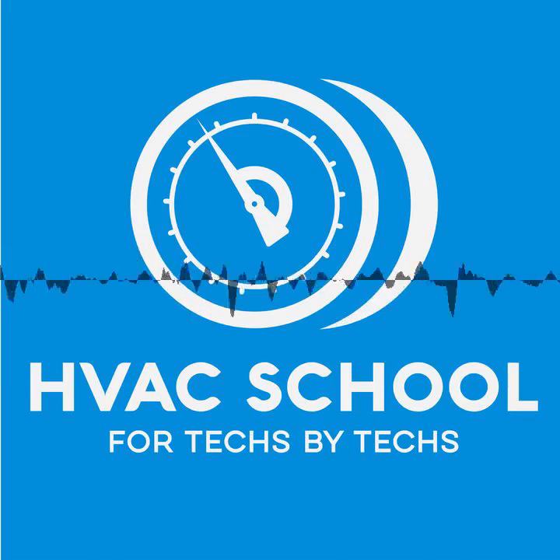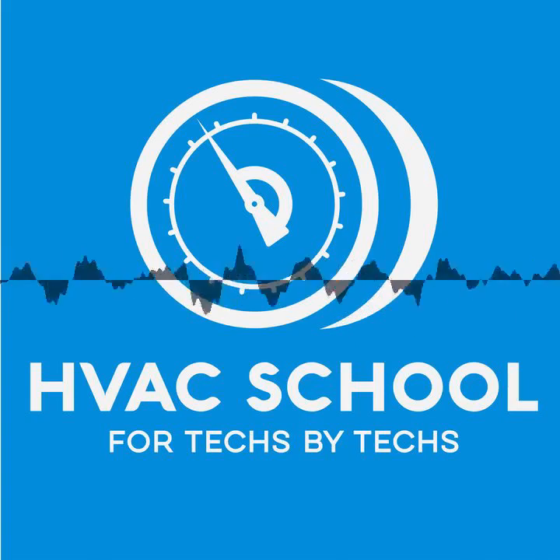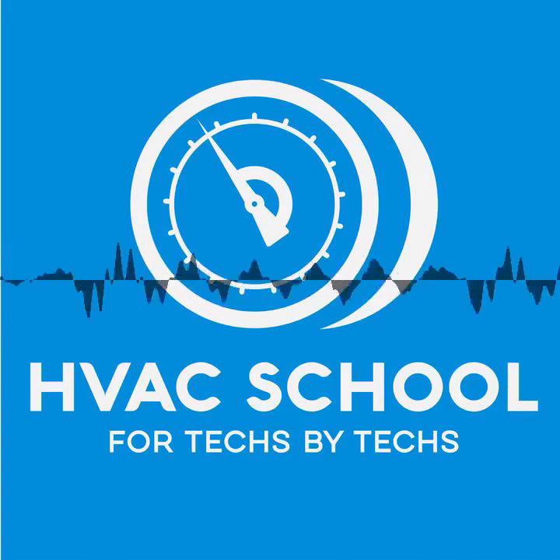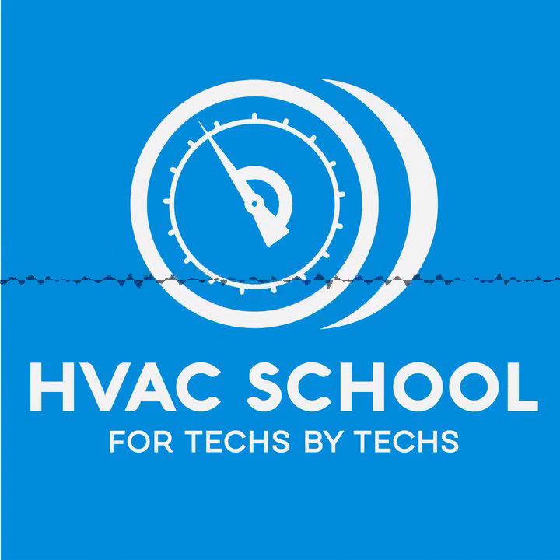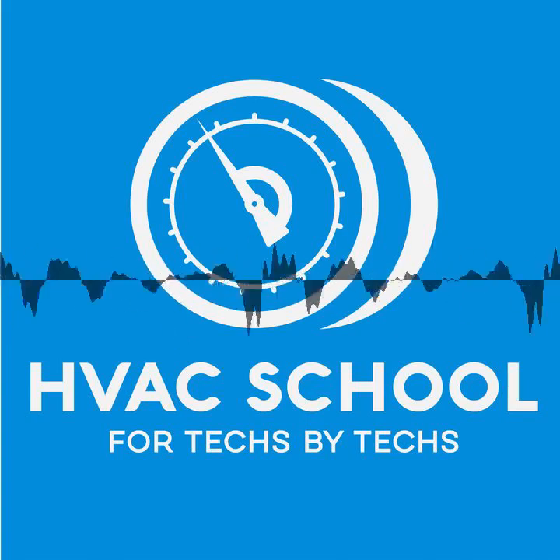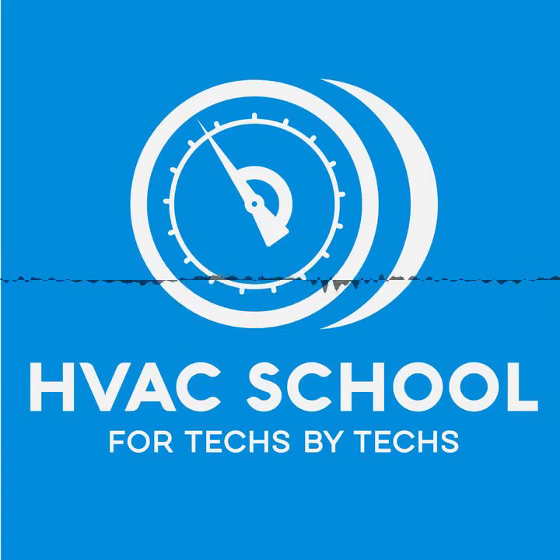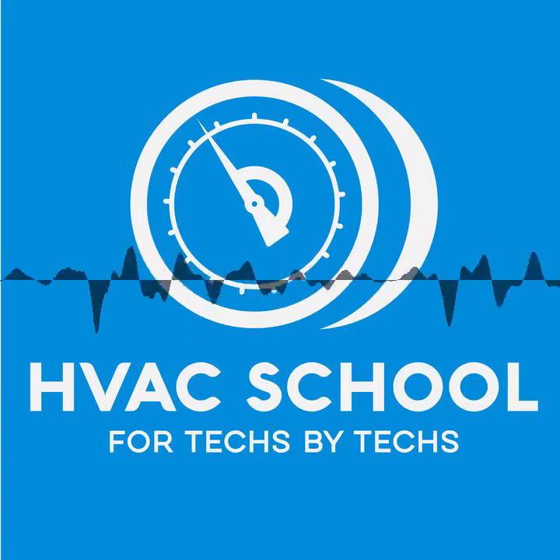Yeah. I think it has to do with energy saving and not getting liquid back, because these cap tube machines don't have receivers or accumulators. So I guess they're trying to assure that they don't get liquid coming back. And like you said, the energy efficiency aspect of it, whichever one is more, I think they're doing it for both reasons, but you'd have to talk to a manufacturer to see why. So it's really hard to look at a suction temperature and see anything that you're used to seeing. And there are also cold wall boxes that don't even have an evaporator fan. So you're going to see really weird stuff going on the low side of systems like that because there's no airflow whatsoever by design.